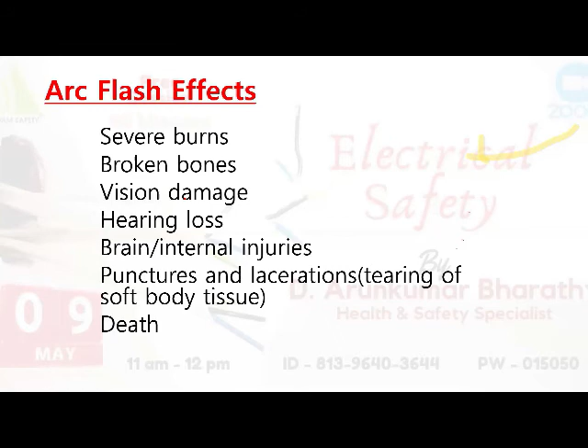Now coming to a very important point: how to protect ourselves from arc flash. Arc flash is nothing but a sudden release of energy with heat, pressure, and radiation. It is called arc flash. Simply put, it creates a lot of problems. Arc flash happens in less than 1 second, but in that time it has the capacity to kill a person. It can create severe burns, vision damage, and a lot of internal injuries.